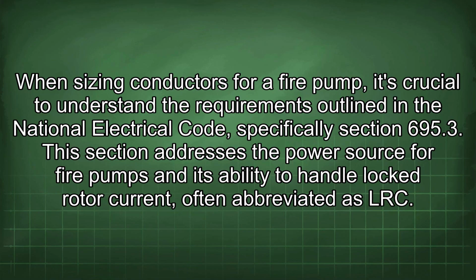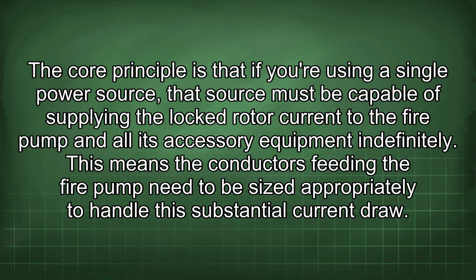When sizing conductors for a fire pump, it's crucial to understand the requirements outlined in the National Electrical Code, specifically Section 695.3. This section addresses the power source for fire pumps and its ability to handle locked rotor current, often abbreviated as LRC. The core principle is that if you are using a single power source, that source must be capable of supplying the locked rotor current to the fire pump and all its accessory equipment indefinitely. This means the conductors feeding the fire pump need to be sized appropriately to handle this substantial current draw.